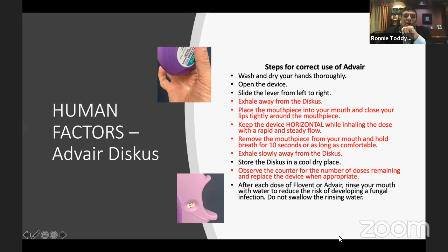Related to manufacturing, obviously, this is a complex process because you have to worry about the formulation, but also now the device, and there are so many parts to this device, so they need to be assembled, etc. In addition to that, one has to consider the usual stuff like the particle size, shape, the electrostatic charges. If while you're manufacturing there are electrostatic issues, then that can be an issue. When you're doing a device assembly, there could be issues if one part or the other is not assembled correctly. So typically when I design any kind of device, you want to make sure that the manufacturing people cannot put it in the wrong manner. That's a very important consideration, and we do something called a process FMEA for that. And then, of course, we talked about already production, humidity, and dose uniformity.